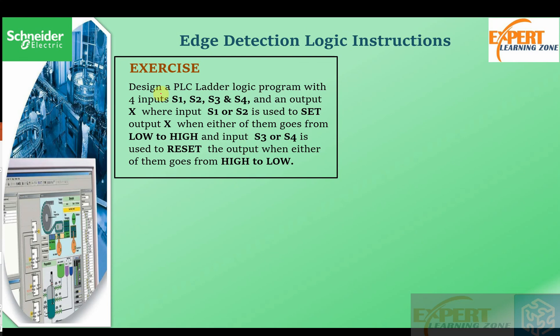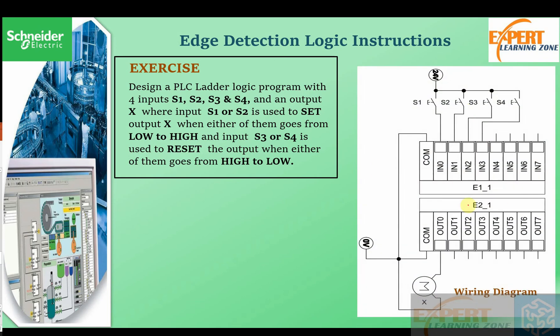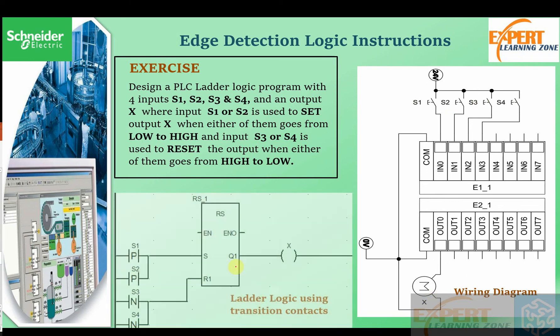Now we look at an exercise: design a PLC ladder logic program with four inputs S1, S2, S3, and S4, and an output X. Input S1 or S2 is used to set the output X when either goes from low to high, and input S3 or S4 is used to reset the output when either goes from high to low. The hardware circuit has switches S1, S2, S3, S4 — all normally open — and output X.